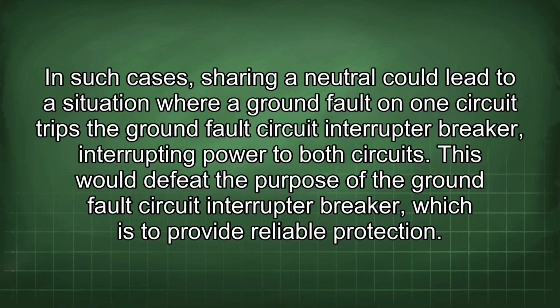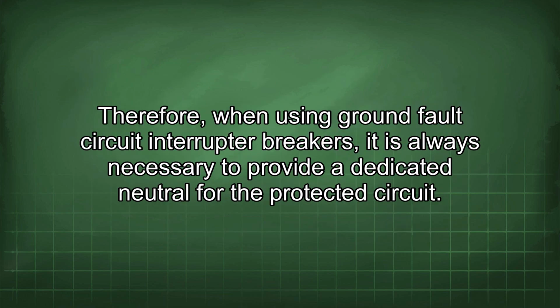In such cases, sharing a neutral could lead to a situation where a ground fault on one circuit trips the ground fault circuit interrupter breaker, interrupting power to both circuits. This would defeat the purpose of the ground fault circuit interrupter breaker, which is to provide reliable protection. Therefore, when using ground fault circuit interrupter breakers, it is always necessary to provide a dedicated neutral for the protected circuit.